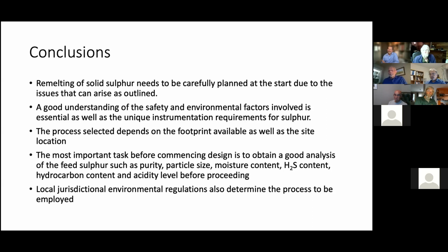So typically, ideally, if you lose steam, you want to drain your sulfur. Right. If you can, drain it, or make sure you have uniform heating all the way through. That's why usually jacketed pipe is the gold standard. They've now come up with channel tubes like Contamination and all that, which are okay for small pipes. But on large pipes, because of the non-uniform heating, if you lose steam, you're in trouble. Same thing with electrical heating. That pipeline that ruptured in the Middle East was electrical heating. So long as it's designed to give you uniform heating all the way through, you're fine. If you don't, then exactly what will happen is what you raised. Yeah. Thank you. Thanks for that.